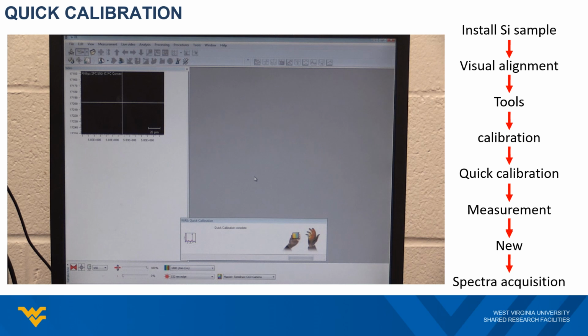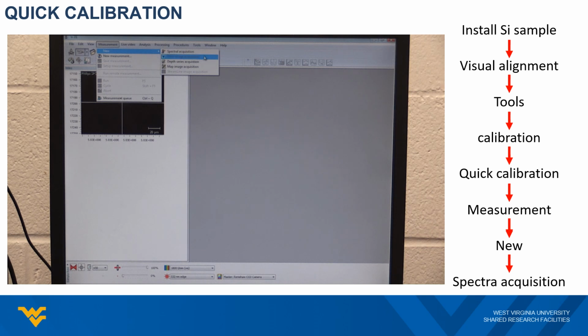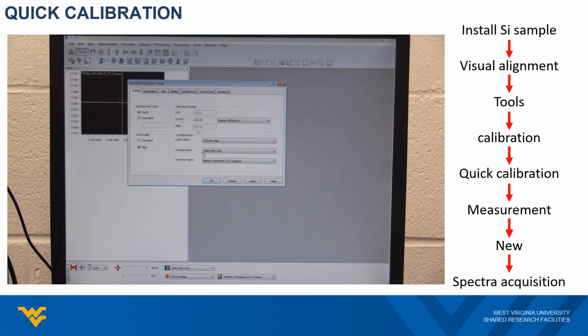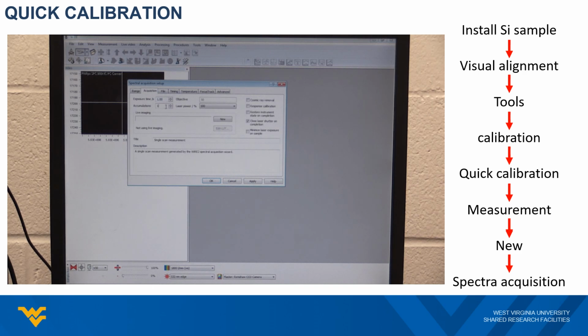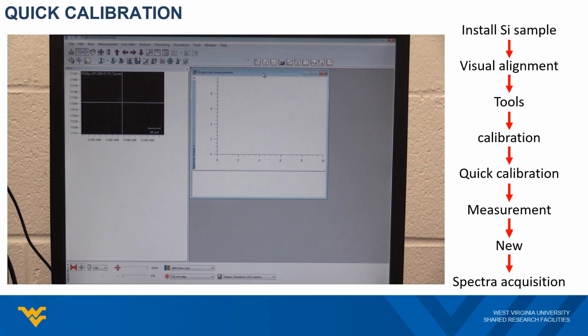After that, you will need to set up a static mode scan centered at 520 inverse centimeter and just choose all the default parameters. Then click Run. It will perform the measurement and just confirm the existence of the 520 inverse centimeter peak from the calibration samples.